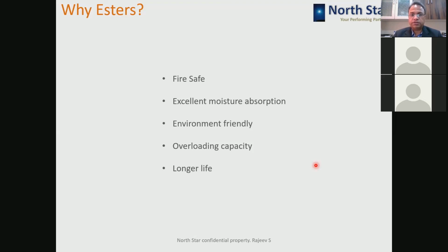Synthetic ester and natural ester, particularly, are 100% biodegradable, and cause no harm to water bodies as well as soil. So soil pollution and water pollution are nil, and they can be used over a high load; that is, the overloading capacity of transformers made from these materials is very high. So in India particularly, where overloading is a common phenomenon, these esters can be very useful as far as premature transformer failure or accidents due to overloading are concerned.